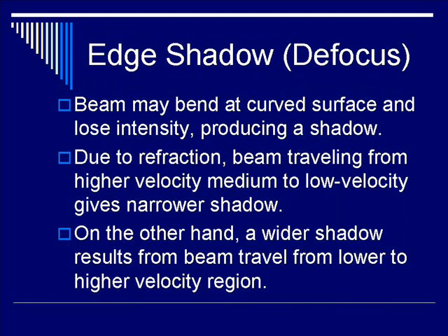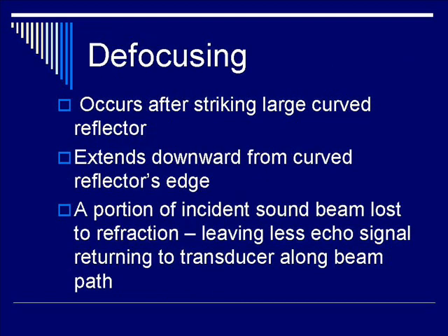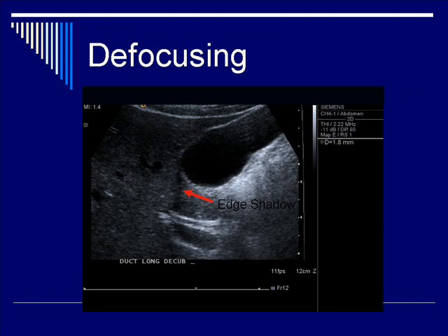The next subcategory of refractive artifact is edge shadowing, otherwise known as defocusing. As beams bend at a curved surface, they lose intensity, producing a shadow around a vessel such as the gallbladder or an organ. A beam traveling from high-velocity to low-velocity medium gives a narrow shadow; from slower to faster, you get a wider shadow. Defocusing occurs classically after striking a large curved reflector, such as a vessel or gallbladder wall, and extends downward from the curved reflector's edge. Because a portion of the incident sound beam is lost to refraction, less echo signal returns to the transducer, explaining the dark anechoic characteristic of the shadowing phenomenon.